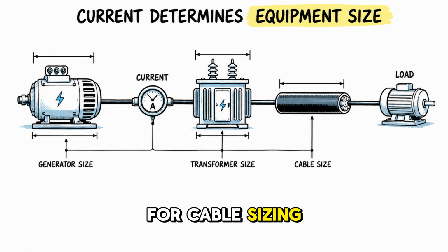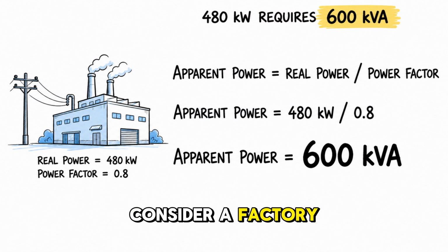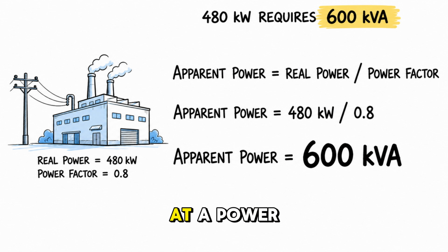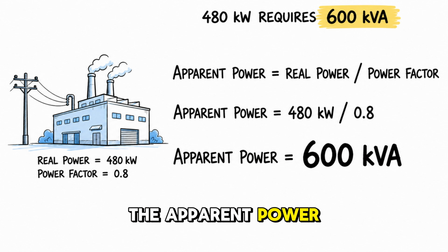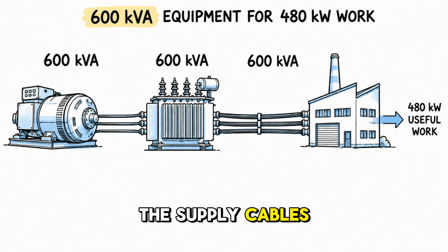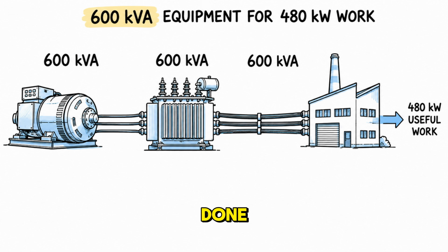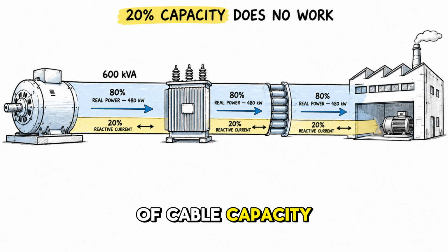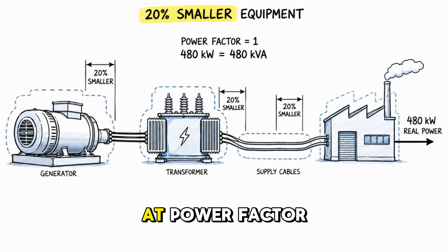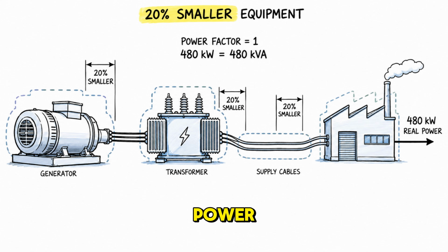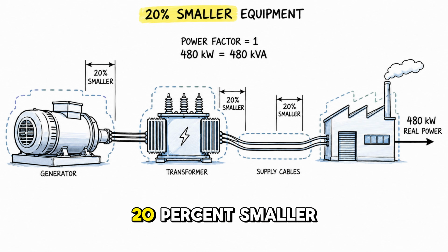This matters enormously for cable sizing, transformer sizing, and generator sizing. Consider a factory drawing 480 kilowatts of real power at a power factor of 0.8. The apparent power is 480 divided by 0.8, which equals 600 kilovolt amperes. The supply cables, the transformer, and the generator must all be sized to carry 600 kilovolt amperes worth of current, even though only 480 kilowatts of useful work is being done. The extra 20% of cable capacity, transformer capacity, and generator capacity is being consumed by reactive current that does nothing useful. At power factor 1, the same 480 kilowatts of real power requires only 480 kilovolt amperes of apparent power. The cables, transformer, and generator can all be 20% smaller.